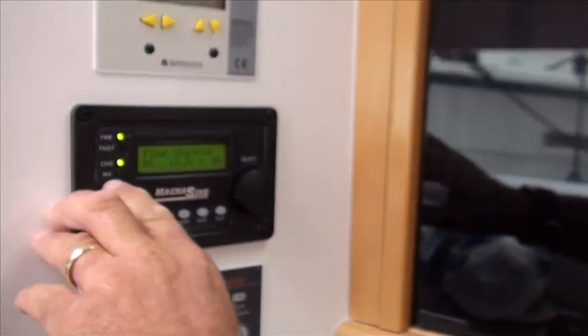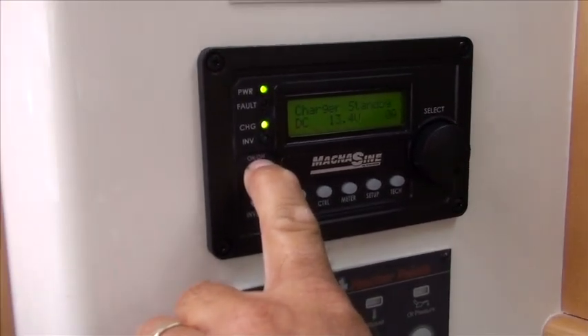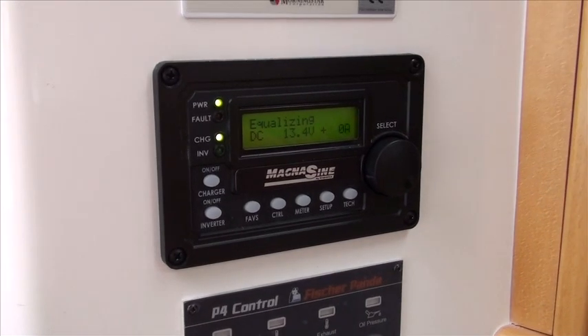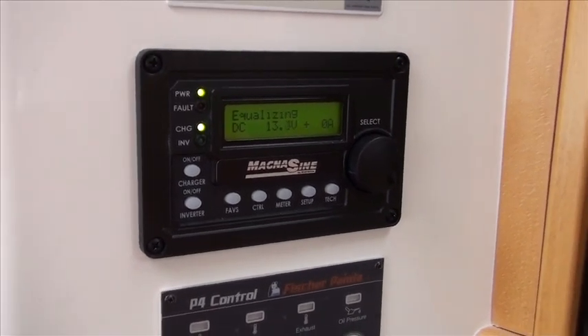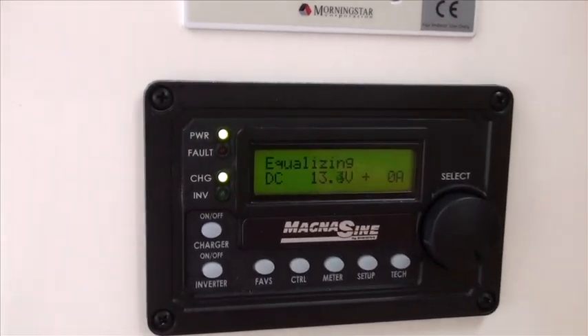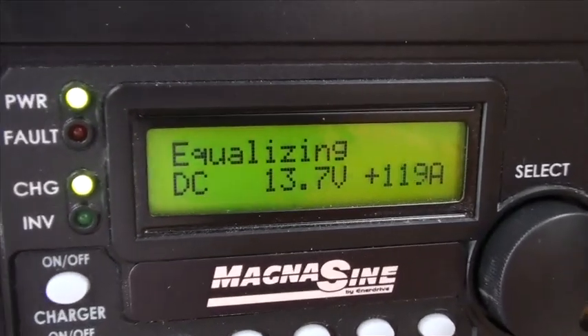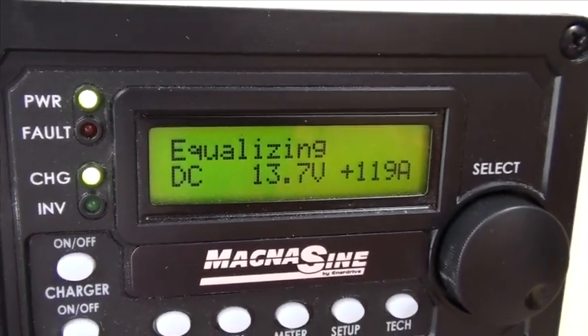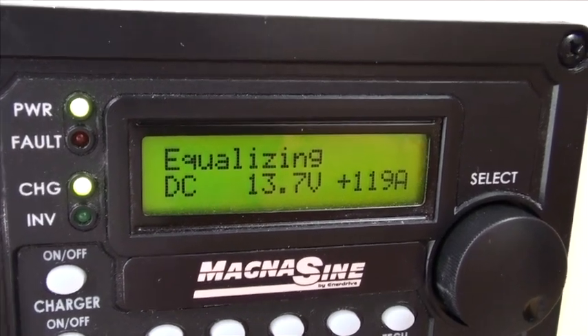In a forced bulk situation, what I've done is I've wound down the equalise voltage. So in order to get it back into a bulk situation, we can just hold down the charger on-off button, and then it'll go to an equalise mode, which will run up to 14.4. Once the batteries can hold it there, charge has now gone to 119.